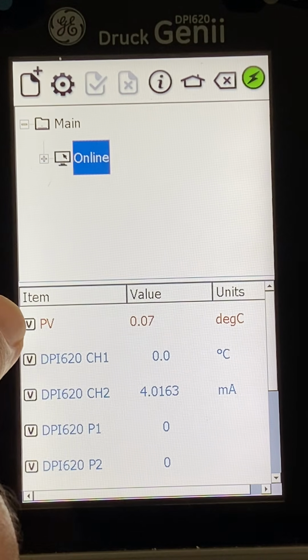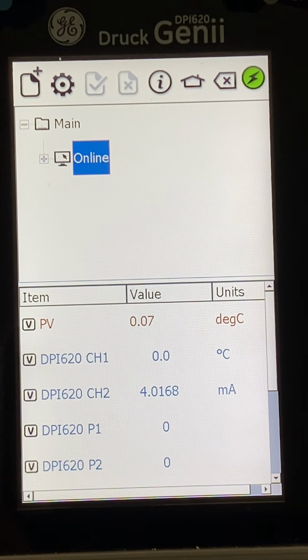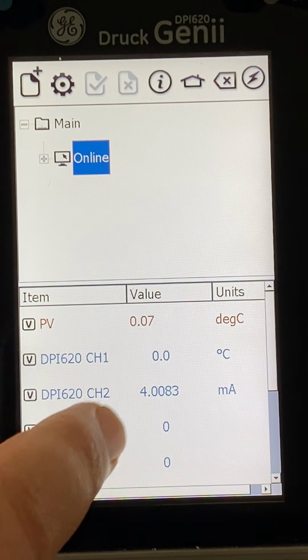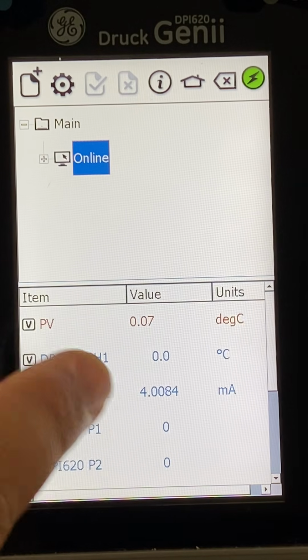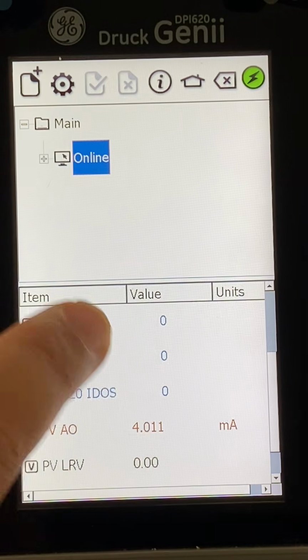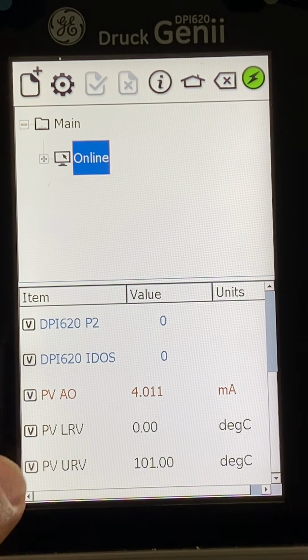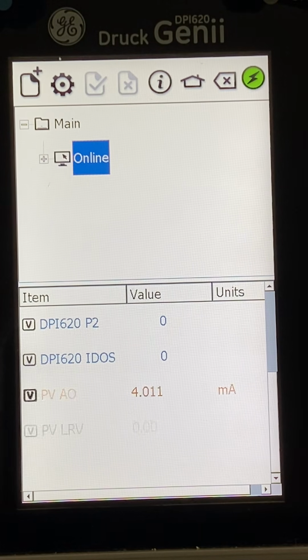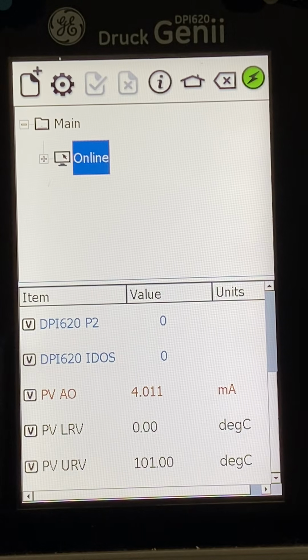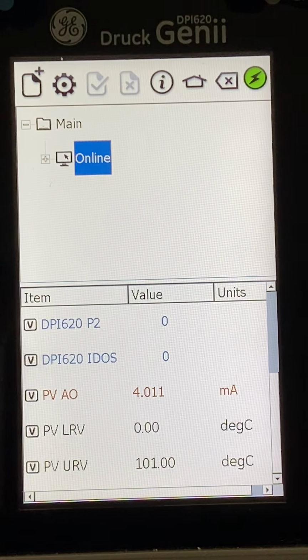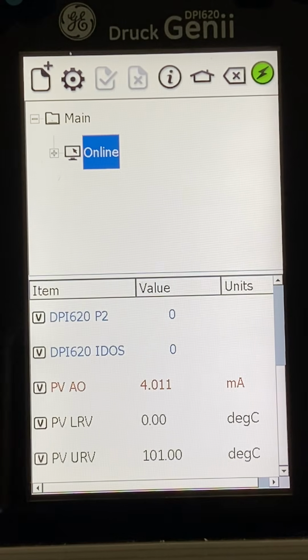Any value in red, I can't play with it. It is the value that came from the transmitter, so it's the measured value. The values in blue are the values which are coming from the calibrator, because we have a calibrator and communicator in the same device. The values in black are the values which can be adjusted on the HART communicator. This will vary from one manufacturer to another, depending on what area the manufacturer is giving you to adjust on HART. So it's always recommended to consult the manual of the transmitter if you wanted to go into details on the HART function.